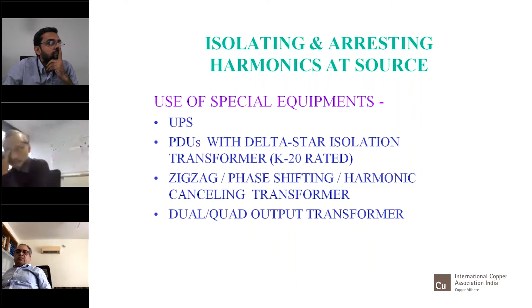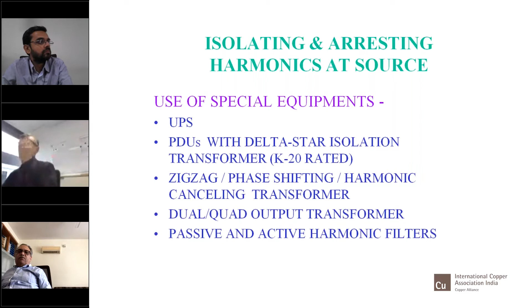Then there is the dual or quad output transformer, where the primary is one and the outputs are 2, 3, 4, because you may sometimes have different kinds of harmonics that you want to mitigate. One equipment is giving this harmonic. It happens in industries: one large machine has some kind of harmonics, and another machine has other harmonics. Instead of putting transformers separately, you can put one and supply 3 machines from different secondary windings. Then there are passive and active harmonic filters.